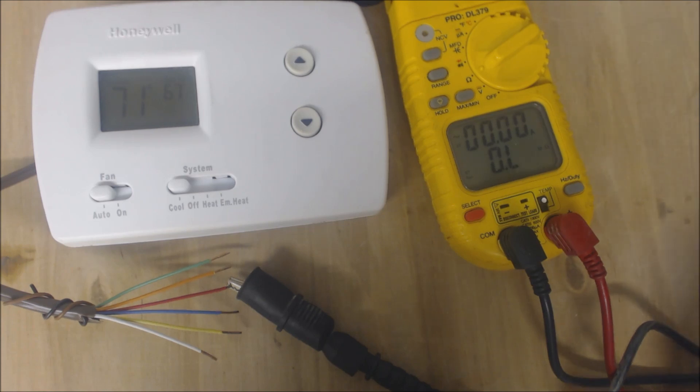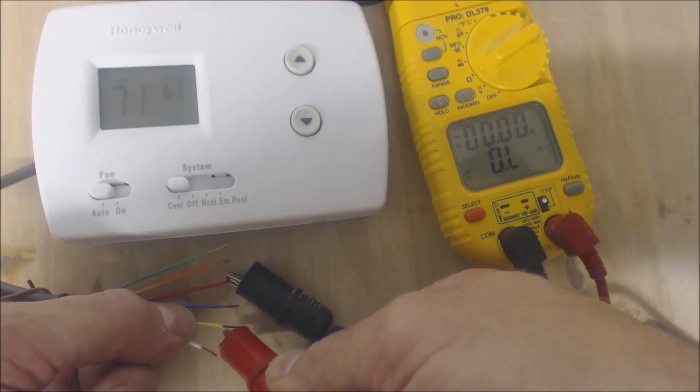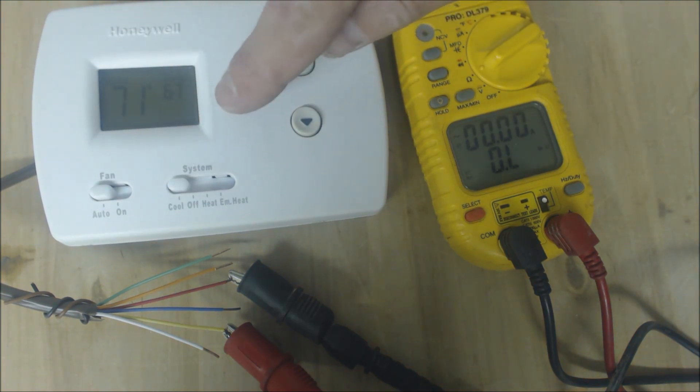What's going to happen is R is going to touch Y, R is going to touch the orange, and R is going to touch G — all of those wires — in order to get cooling on. You need to power the reversing valve in order for the refrigerant to change direction and go into cooling mode.